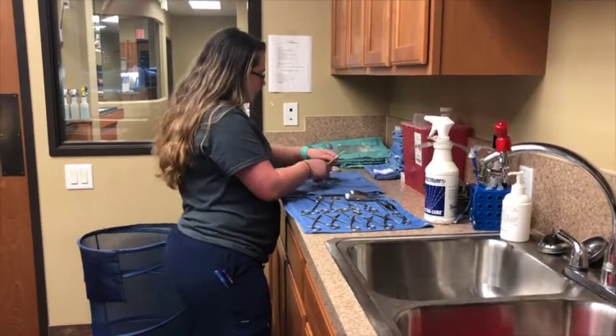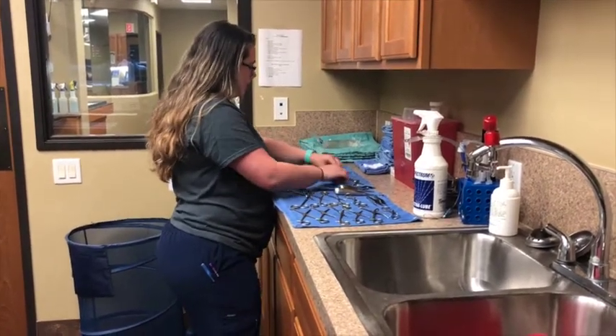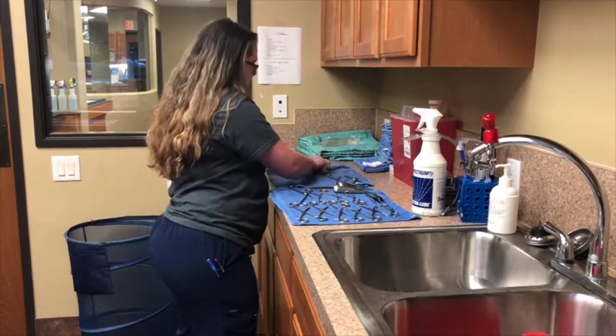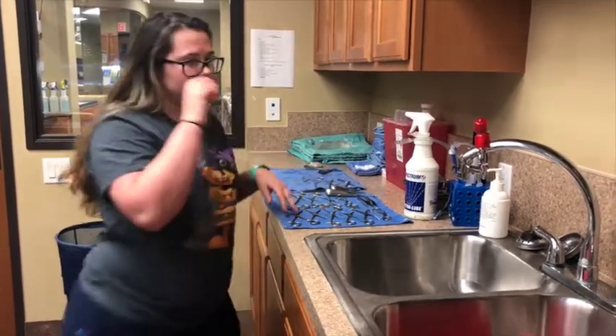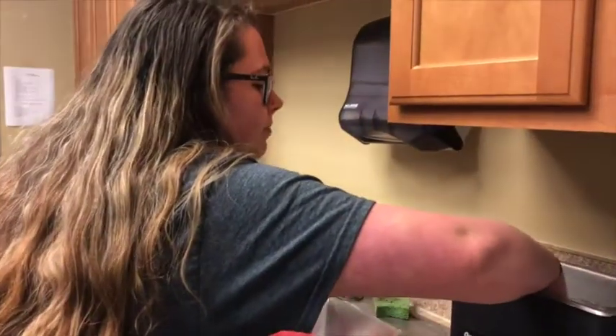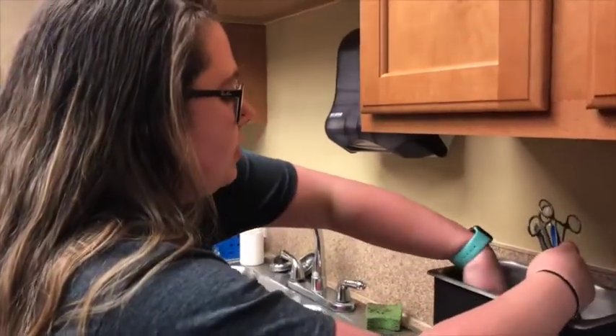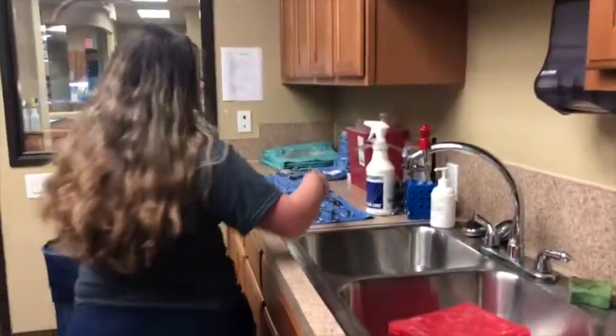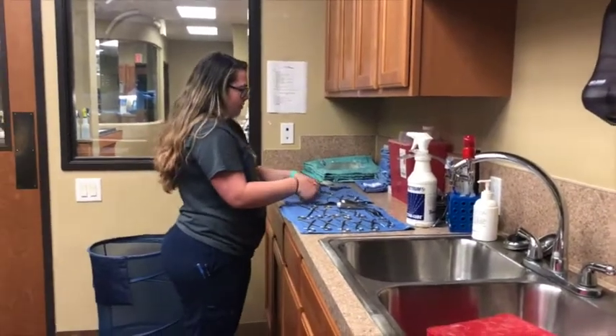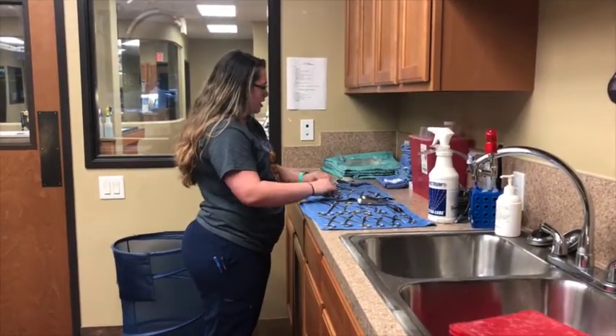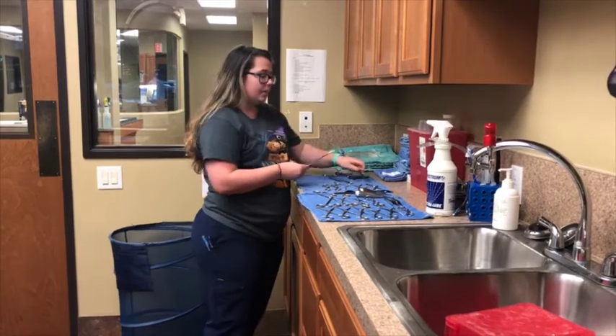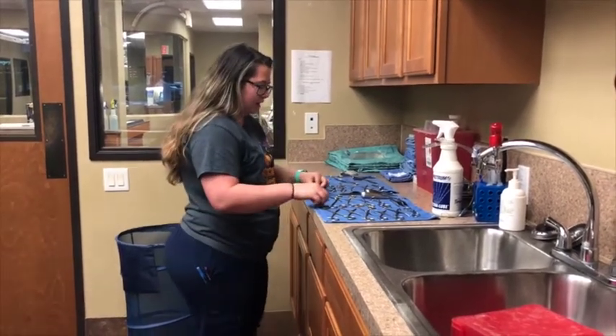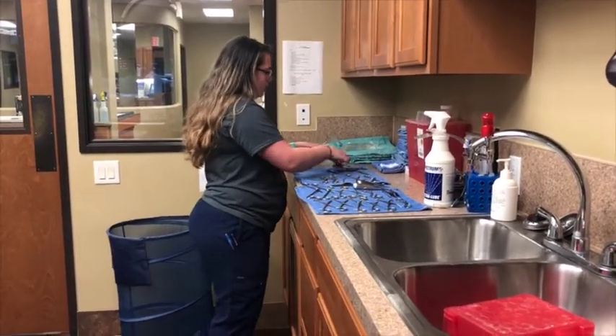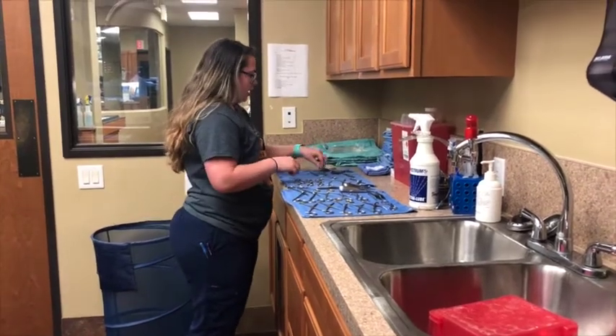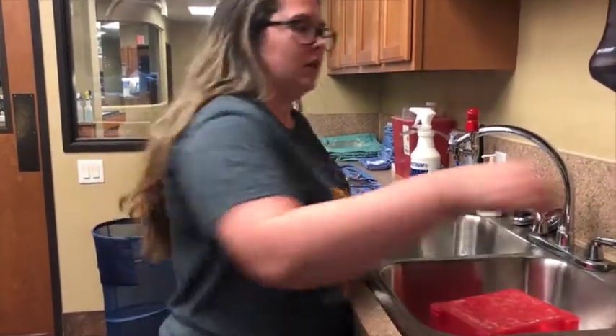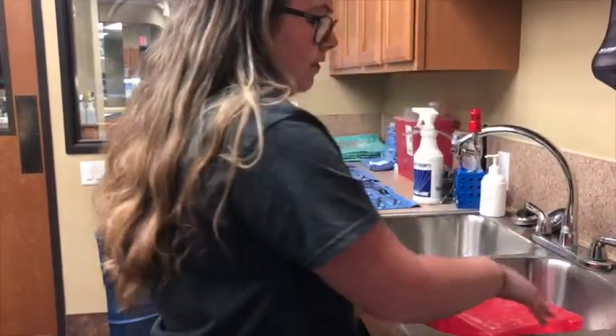And we do have 2 towels here because we have multiple instruments in there for different procedures. And you don't want to let them sit in the ultrasonic cleaner for too long because they will rust if they're sitting in the water for too long. So just make sure you get them out as soon as that cycle is done and the water has cooled. It does heat up, so don't reach in there when the water is still hot. You will burn yourself, so just wait for it to completely finish. Just don't leave them in there overnight. Make sure you have everything.